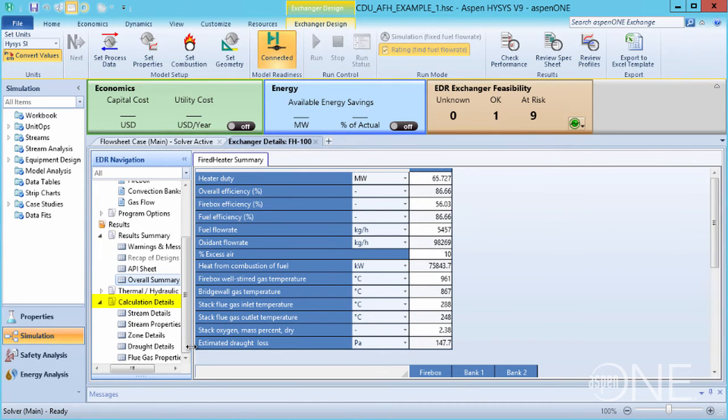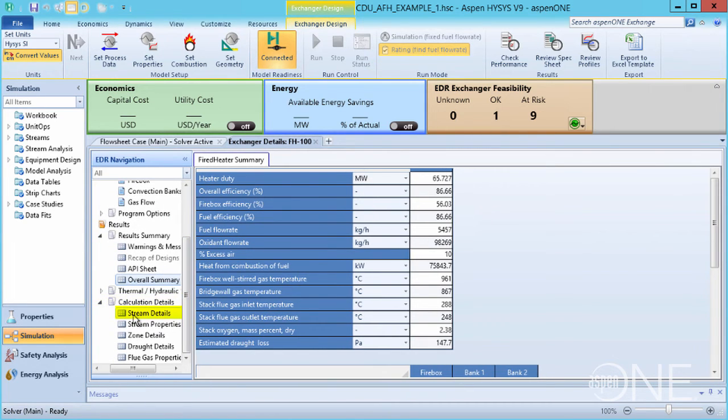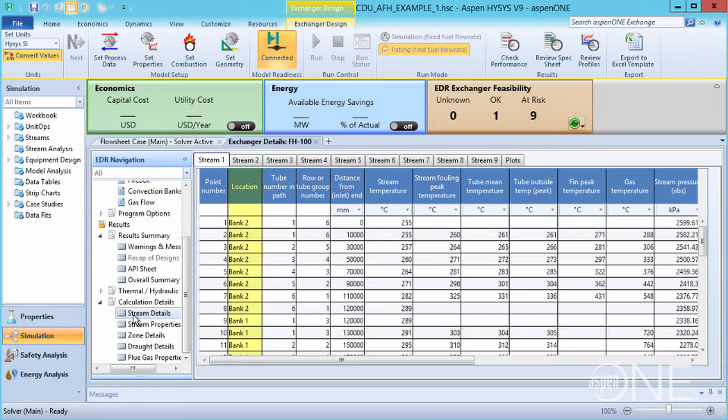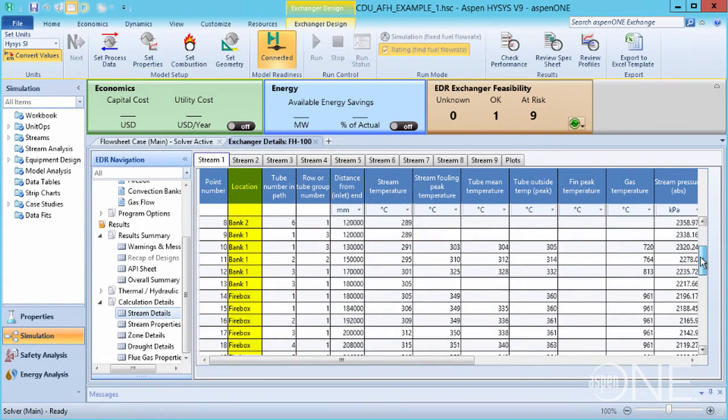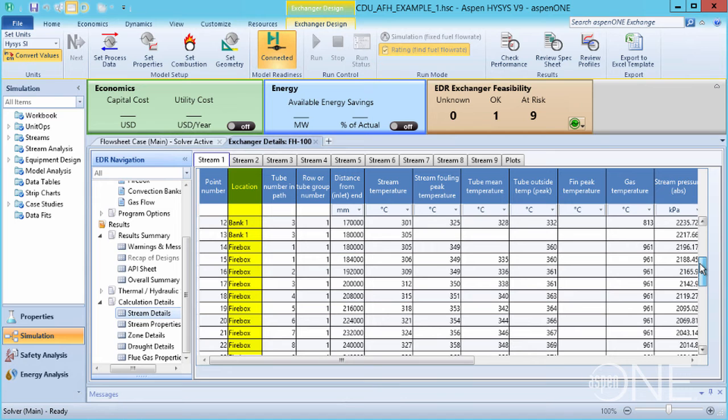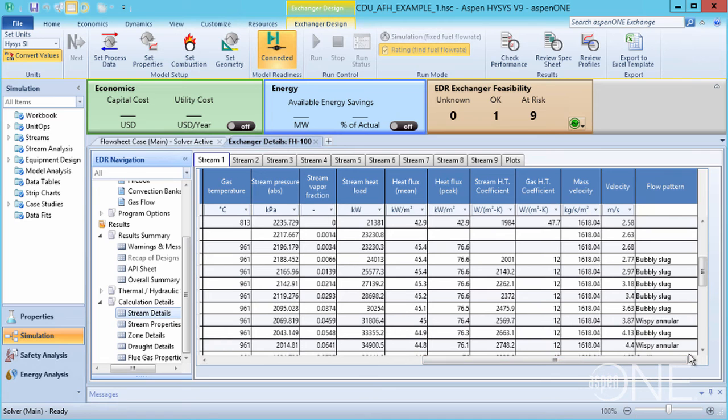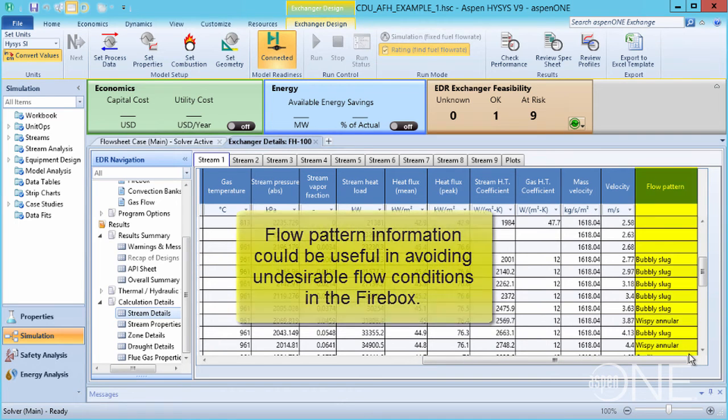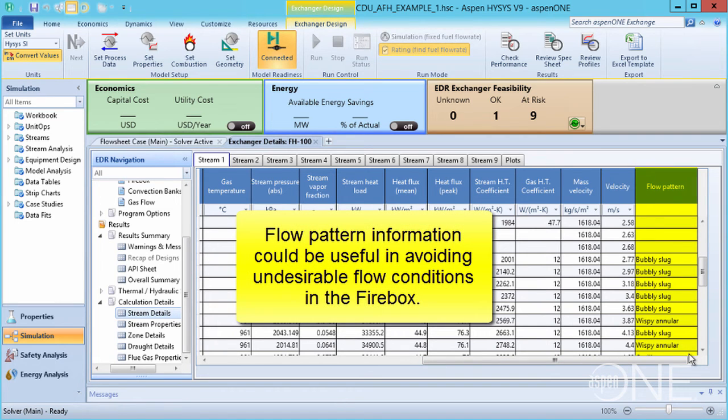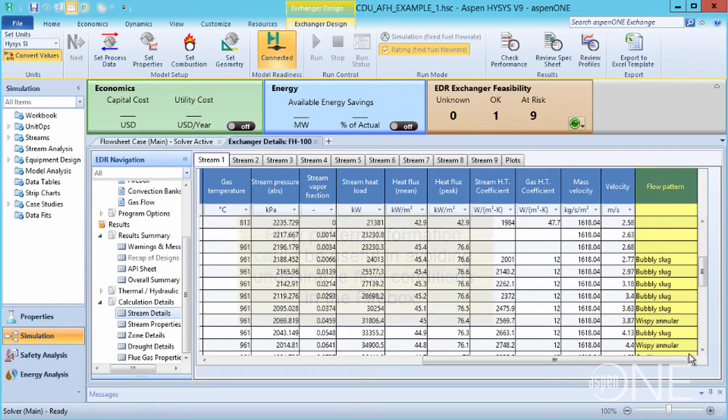Here, under Calculation Details, Stream Details, we can see step-by-step details through the tubes of the convection section, the tubes of both convection banks, and through the firebox. We get detailed local information on what's occurring on a tube-to-tube basis, and this includes two-phase flow pattern information, which could be useful in avoiding undesirable flow conditions in the firebox.